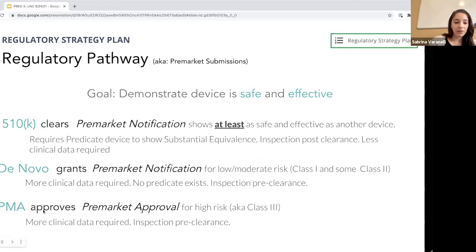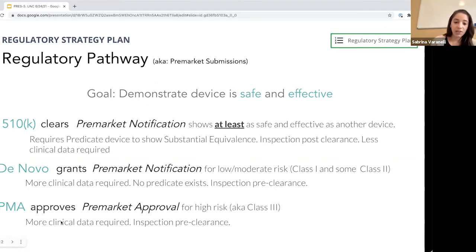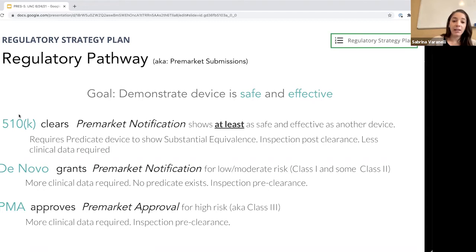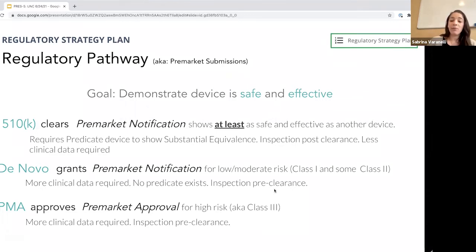The third major regulatory pathway is called a PMA, used for high risk devices. A lot of clinical data is required — more than DeNovo. One critical difference between these three pathways is when your manufacturing facility is inspected by the FDA. When you're getting a 510k, you're allowed to have your facility inspected after you start selling your product. If you're getting a DeNovo or a PMA, you must have your facility inspected before you can start selling.